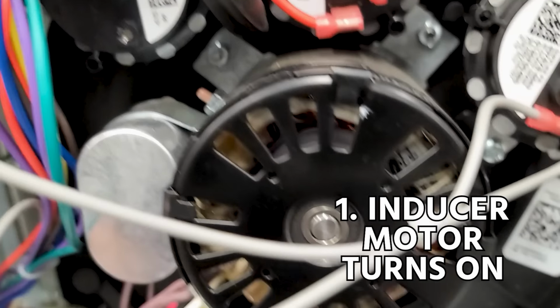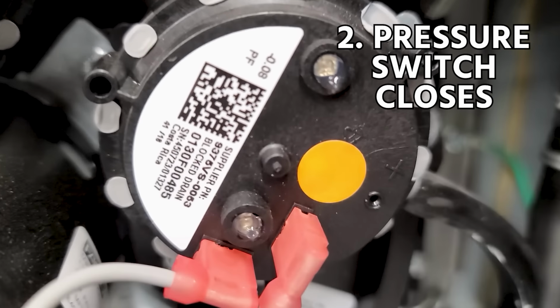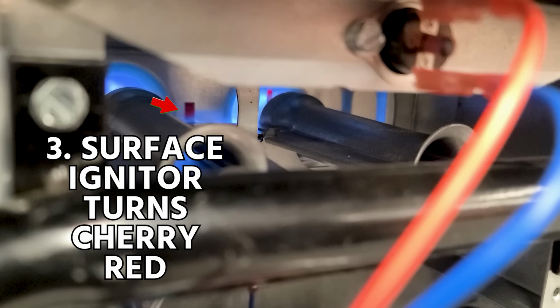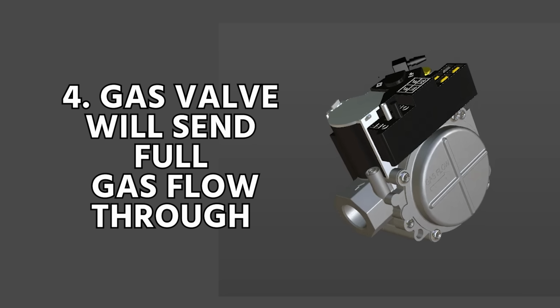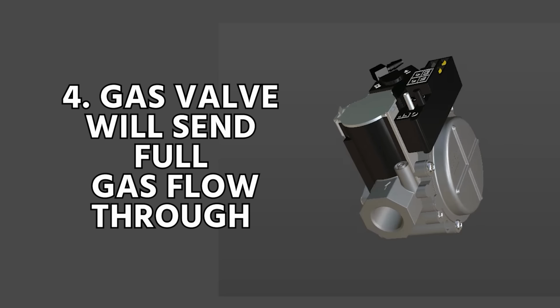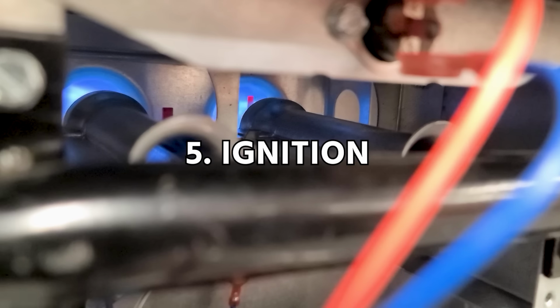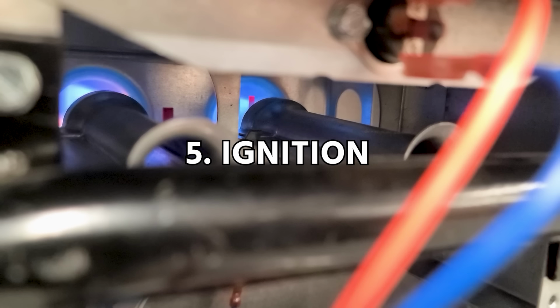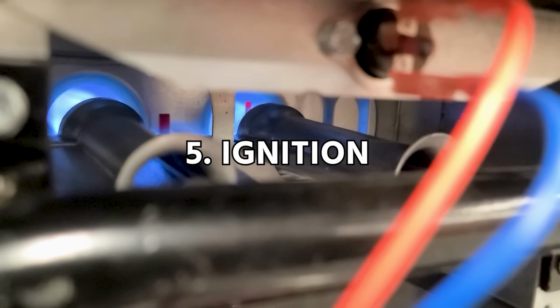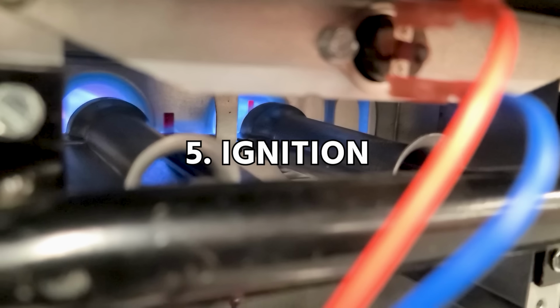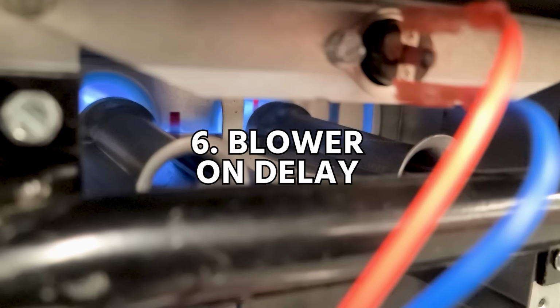So first step, inducer motor turns on, pressure switch closes, hot surface igniter turns cherry red. Then after that's cherry red, what's going to happen is the gas valve is going to send the full gas flow through. So the fourth step is the gas valve. Then you have your ignition. So step 5, you have your flame rectification process, proving the flame. Then 6 is the blower on delay.